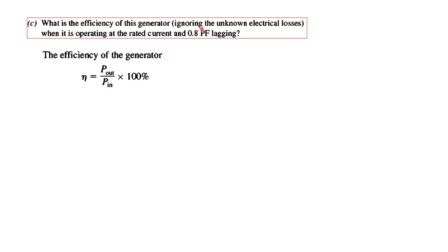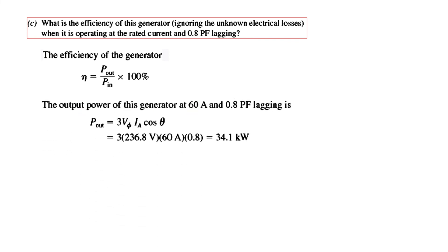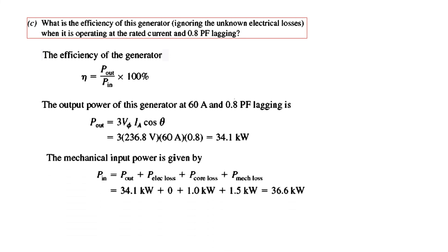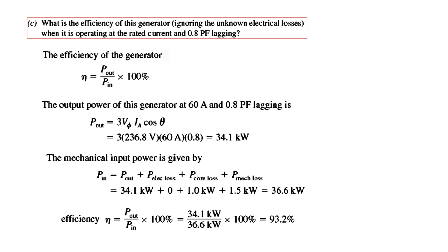Part C: Find the efficiency at 0.8 power factor lagging, ignoring unknown losses. Efficiency = P-out / P-in. P-out = 3 × V-phase × Ia × cos θ = 3 × 236.8 × 60 × 0.8 = 34.1 kW. P-in = P-out plus all losses; with the given friction/windage losses included, P-in = 36.6 kW. Efficiency = 34.1 / 36.6 = 93.2%.